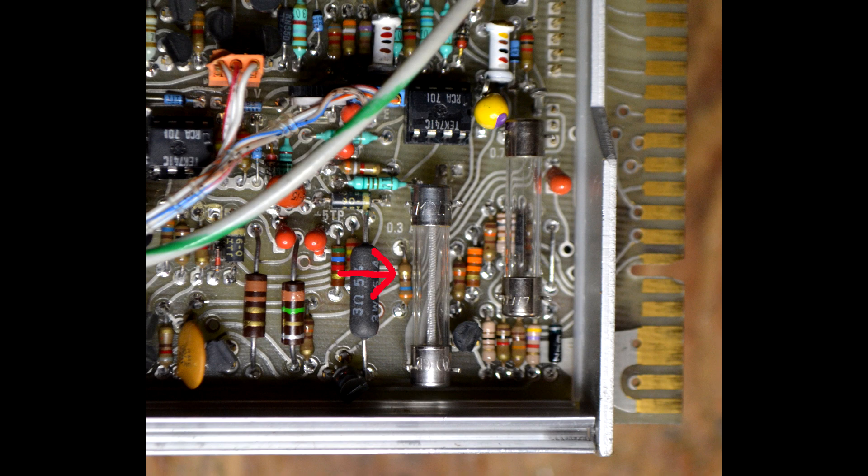The plus and minus 20 volt and plus 5 volt supplies were all correct. Fuse F800, a 3 tenths amp slow blow, was open.